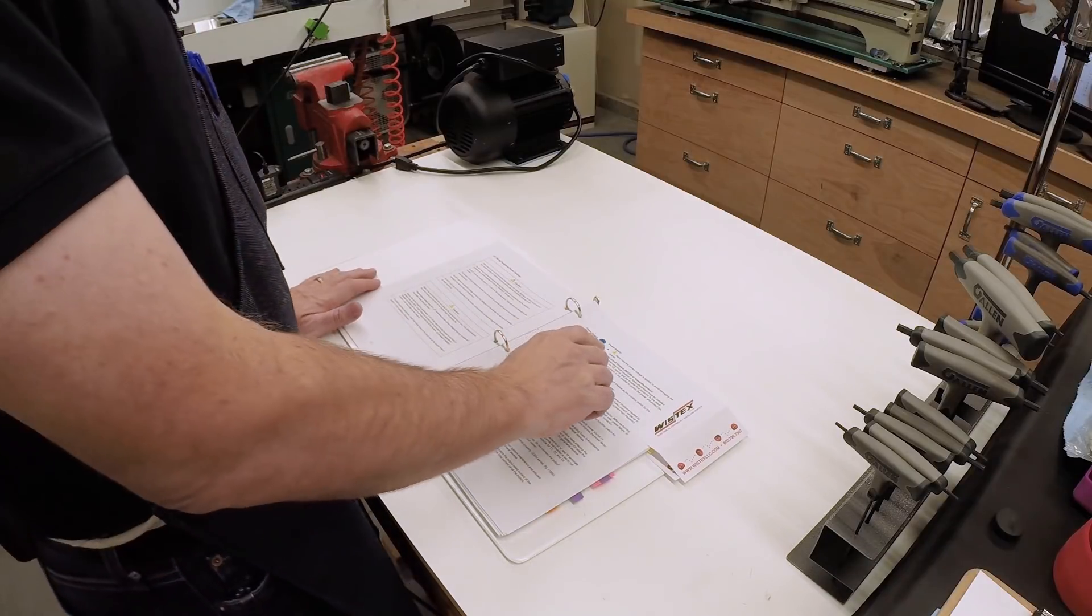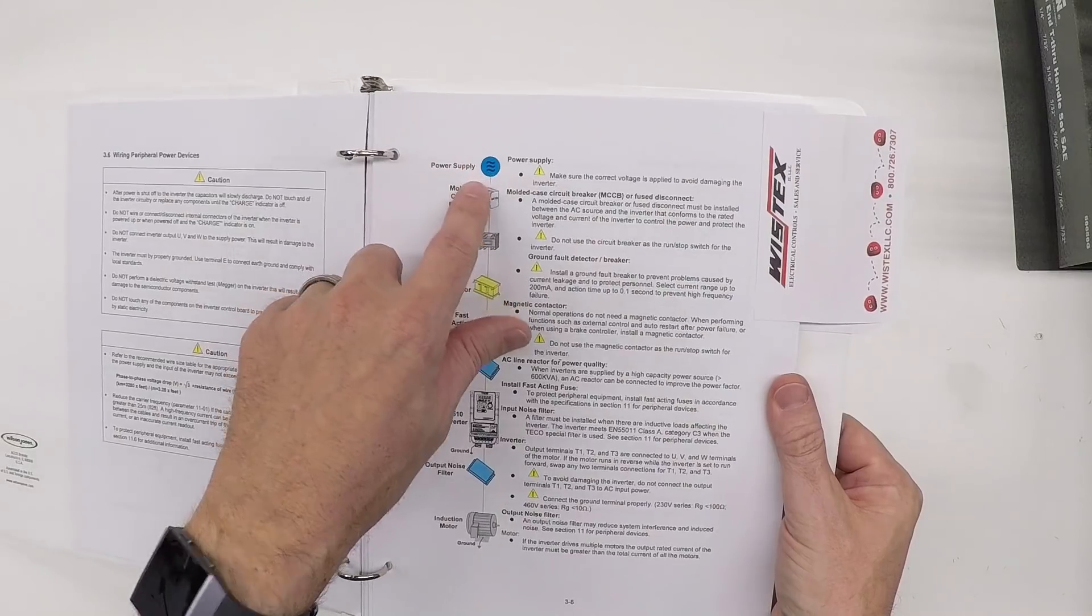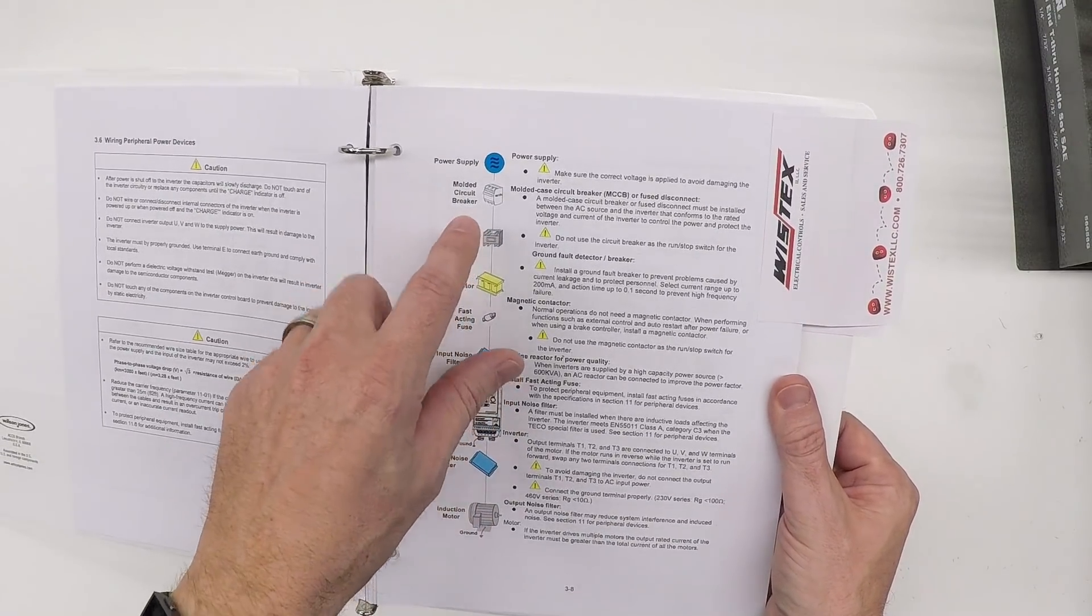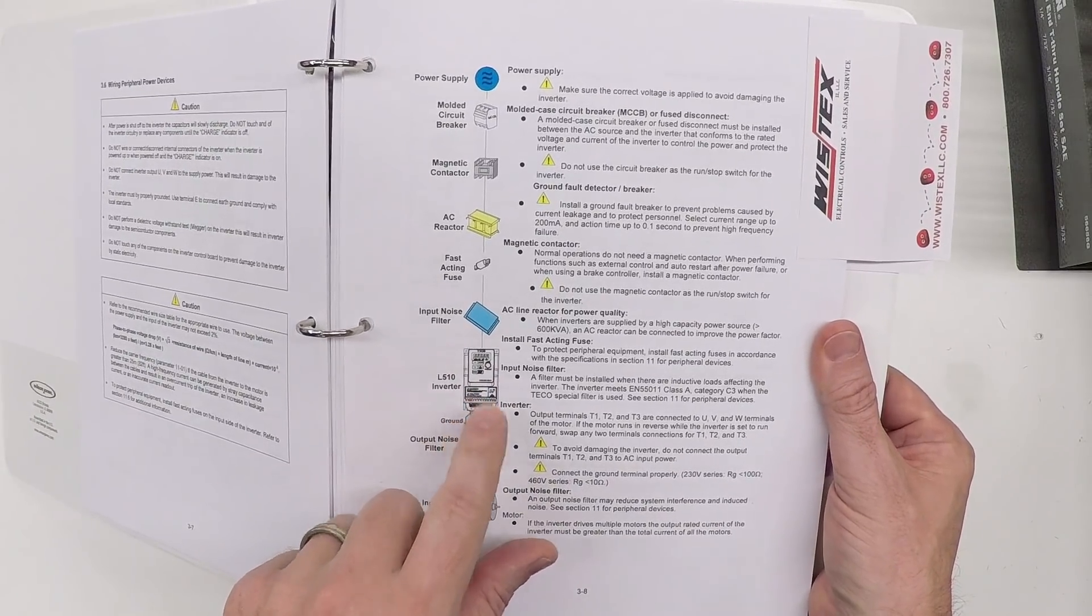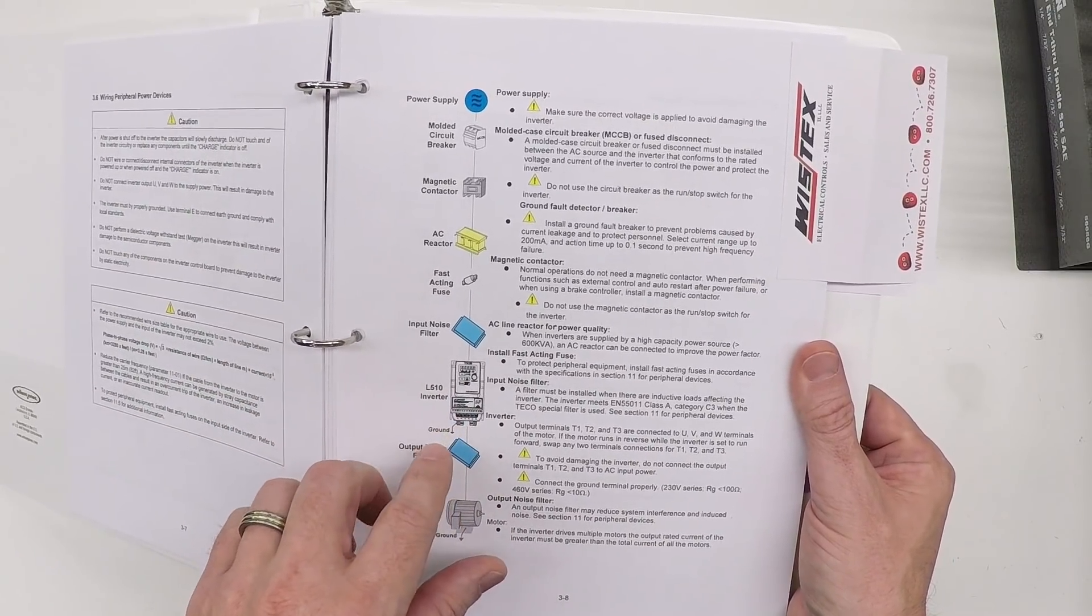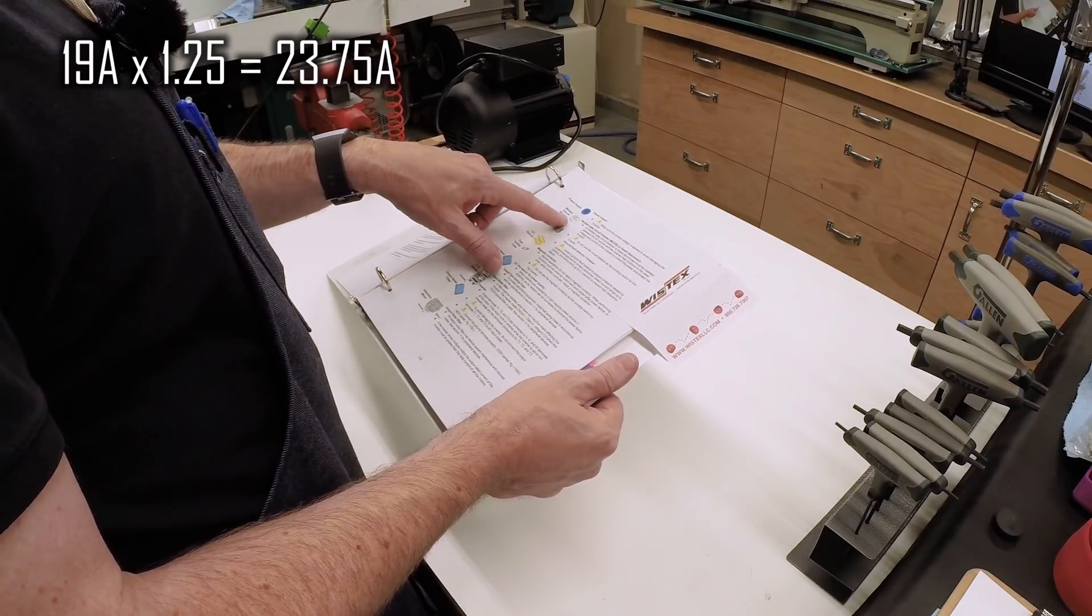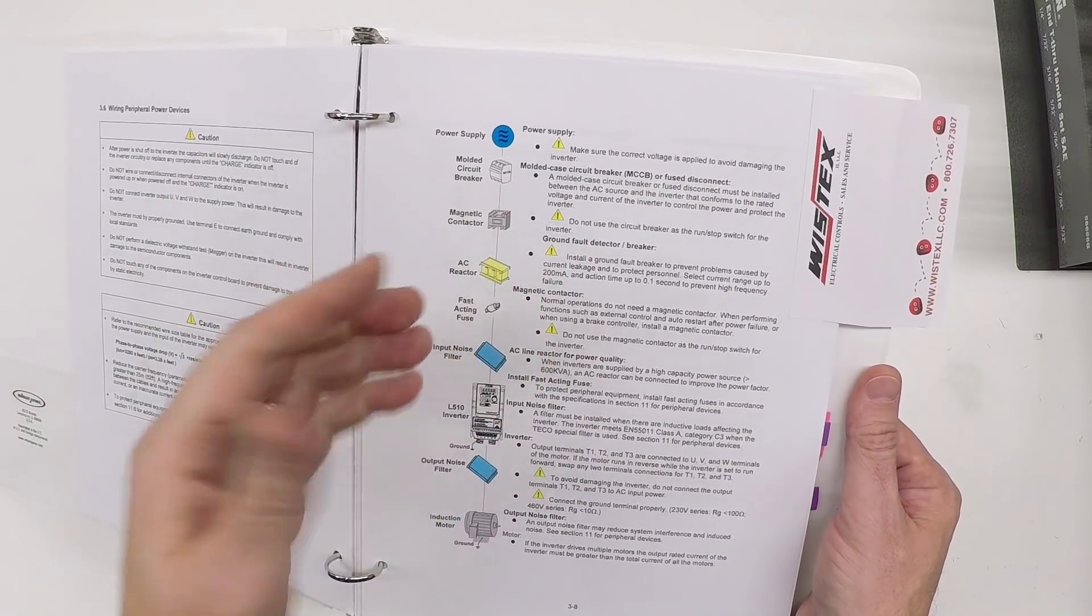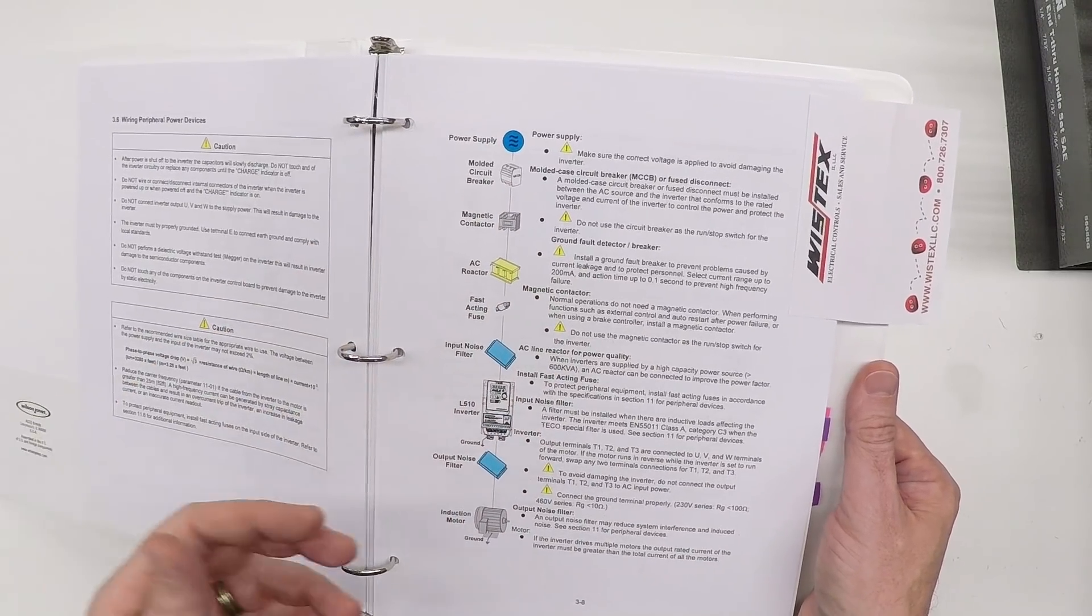Let's start with the circuit breaker. In this case, I have the inverter in the box and it's wired up to a power supply that already has a circuit breaker. Why would we need another one? Well, we probably don't to prevent a fire, but the one thing here is that the circuit breaker in the wall is 30 amps, and this device, the inverter, is only drawing 19 amps maximum according to the spec. So if you take that 19 amps, multiply it by 1.25 and then round up to the nearest available circuit breaker size, you would want a 25 amp breaker on here. Is a 25 amp breaker really that different from a 30 amp breaker when you're talking about an overload situation like this with 10 gauge wire? Yeah, probably not, but we might as well.